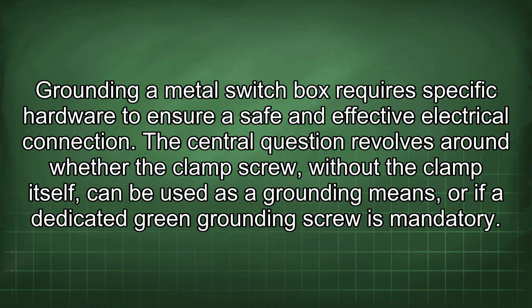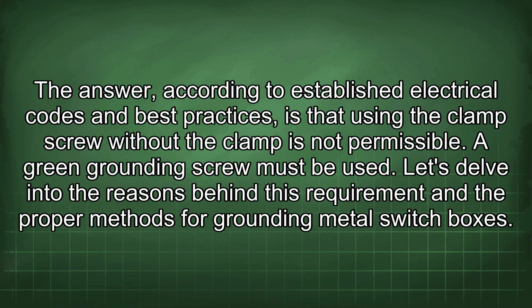Grounding a metal switch box requires specific hardware to ensure a safe and effective electrical connection. The central question revolves around whether the clamp screw, without the clamp itself, can be used as a grounding means, or if a dedicated green grounding screw is mandatory. The answer, according to established electrical codes and best practices, is that using the clamp screw without the clamp is not permissible. A green grounding screw must be used. Let's delve into the reasons behind this requirement and the proper methods for grounding metal switch boxes.